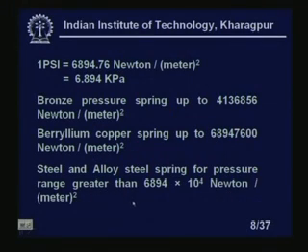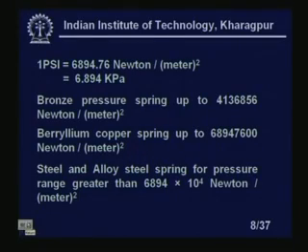Sometimes the range of this particular instrument depends not only on the range we should consider, but also on the environment. Suppose I am measuring the pressure of corrosive liquids. In that type of situation we have no choice other than using a stainless steel C tube, right. So these are the different materials of the C type Bourdon tubes, okay. These are the different materials.